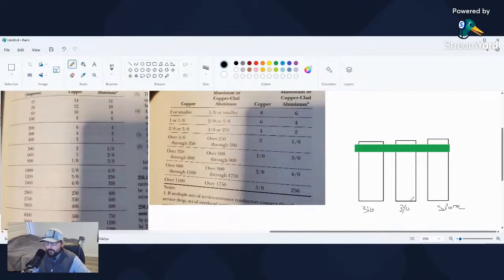If you've got a fault in this pipe here, you've still got to be able to clear and get the current back to the source. So this wire needs to be big enough to carry the whole load, because you're not just carrying the load of one 3/0, because this is all a set. This is all going to the same spot. So just like you have all these sets of wire to make up the total, you've got one ground size to make up the total. So you need to be able to clear that fault with a big enough wire before it just disintegrates itself, overheats, melts, breaks, whatever. You need to have a reliable path back to the source. So that's why you got to upsize your ground.